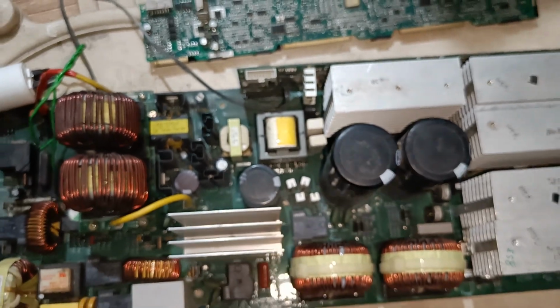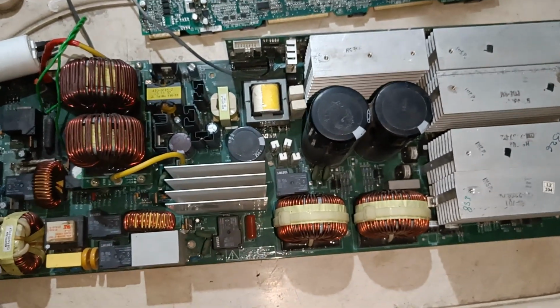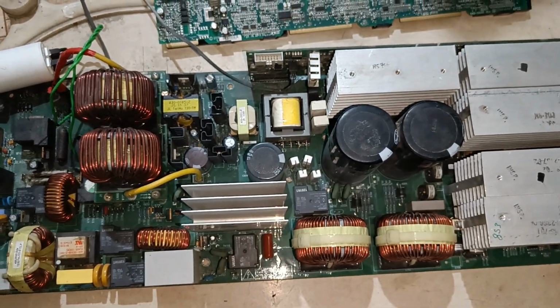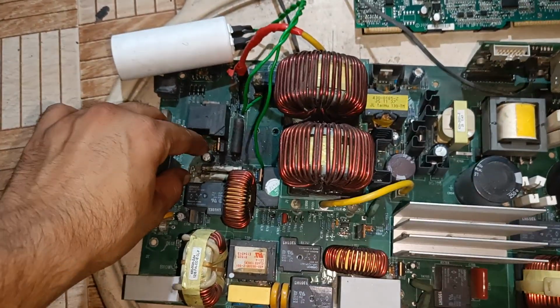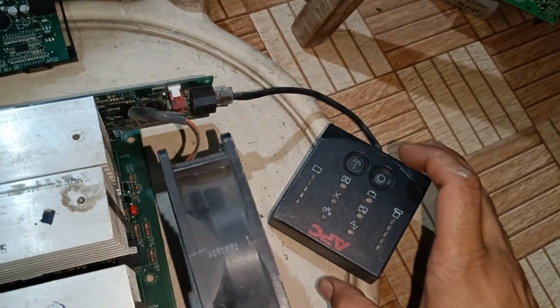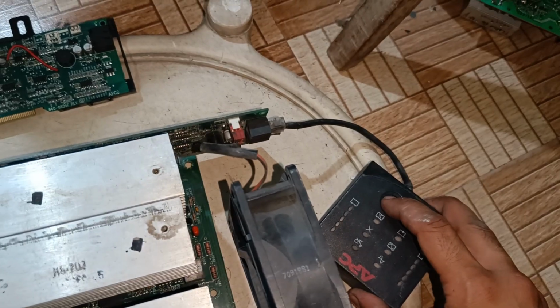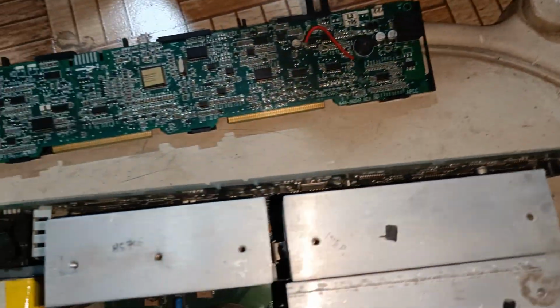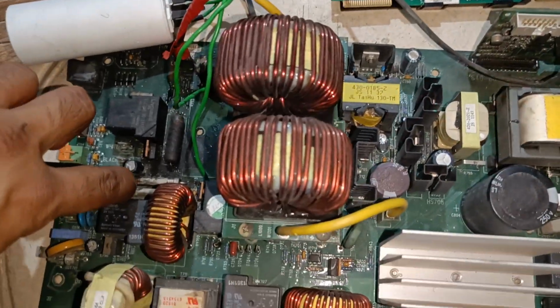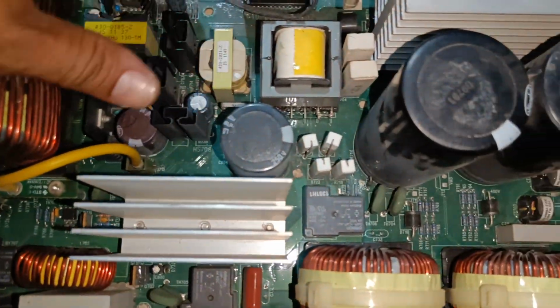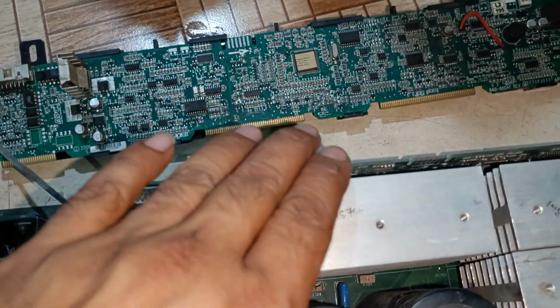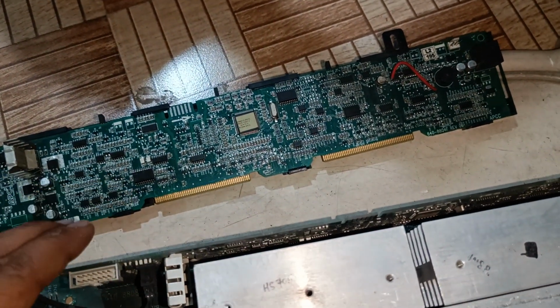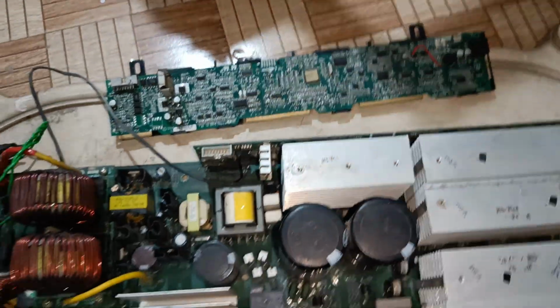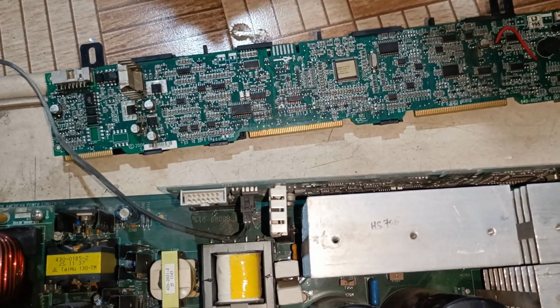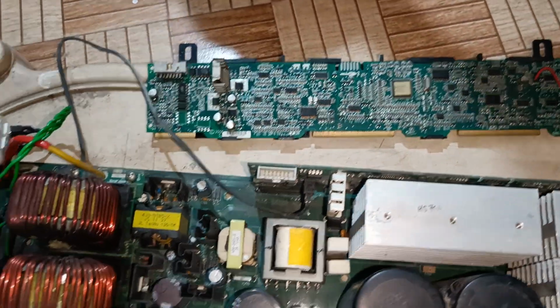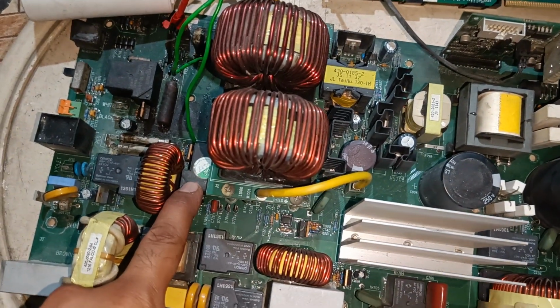This is the case of input. Now, when the input supply fails and we don't have input voltage, how does this UPS work? We have battery voltage here, and when we press the button from the front panel, it closes the switch, and the voltage here is also fed to the control card. When the circuit is closed, the voltage is analyzed by the control card itself, and it senses the battery voltage is sufficient to run the UPS, then it turns on this relay.